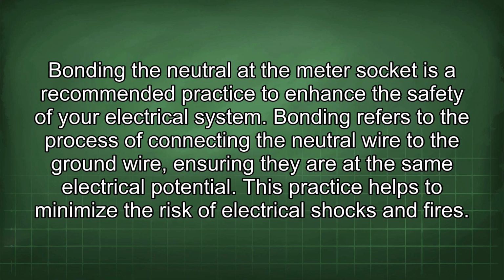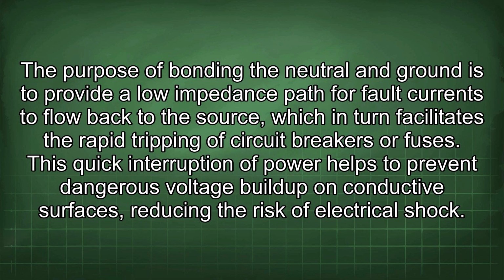Bonding the neutral at the meter socket is a recommended practice to enhance the safety of your electrical system. Bonding refers to the process of connecting the neutral wire to the ground wire, ensuring they are at the same electrical potential. This practice helps to minimize the risk of electrical shocks and fires. The purpose of bonding the neutral and ground is to provide a low impedance path for fault currents to flow back to the source, which in turn facilitates the rapid tripping of circuit breakers or fuses. This quick interruption of power helps to prevent dangerous voltage buildup on conductive surfaces, reducing the risk of electrical shock.